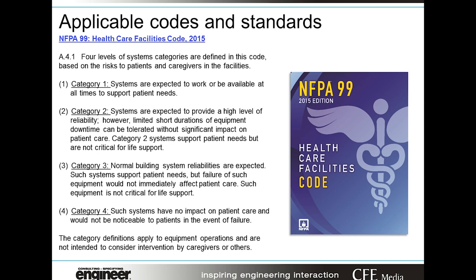NFPA 99 is a guideline that helps us understand the criticality of the facility with respect to the nature of healthcare being delivered and its various risks. A Category 1 facility expects that systems are operable regardless of what happens, to support patient needs — a very reliable type of system. Category 4 is the other end of the spectrum, where if such systems fail they will have no impact on patient care, and thus the investment in mechanical and HVAC systems doesn't need to be as mindful of reliability.